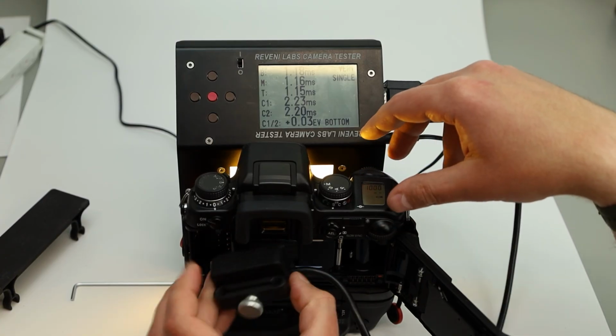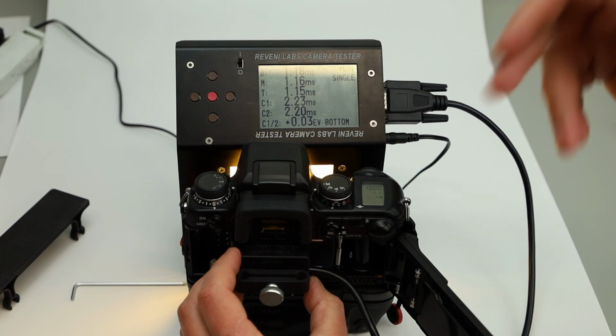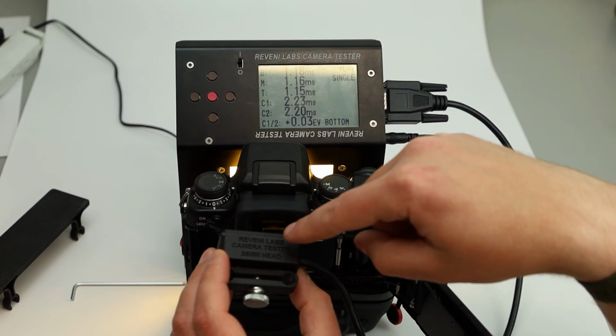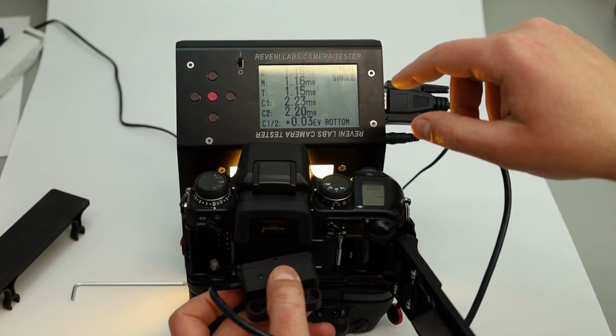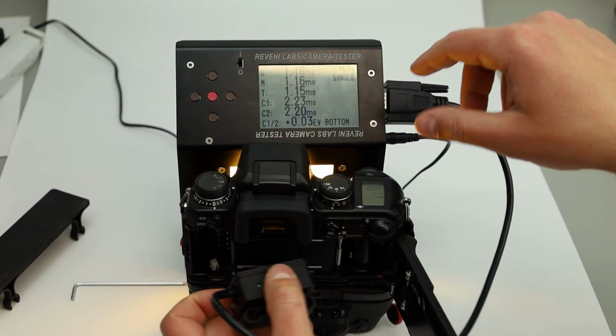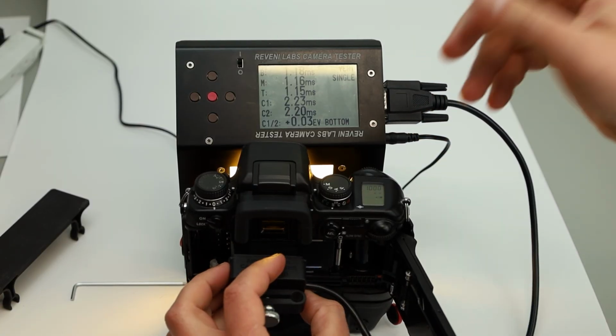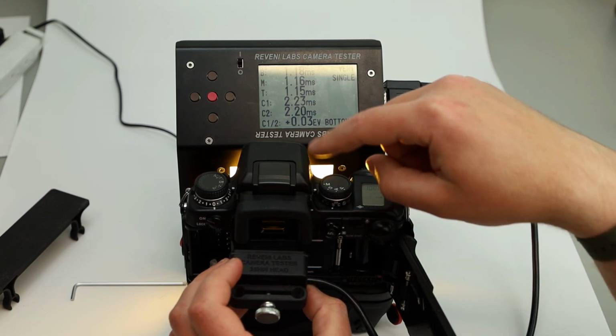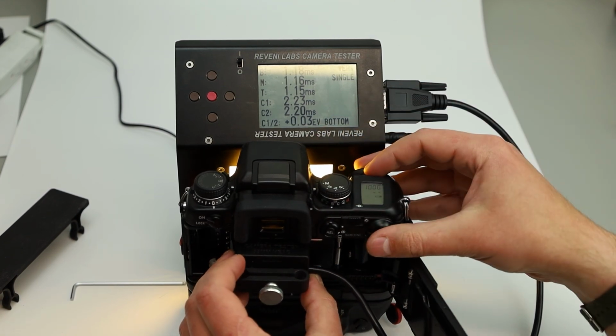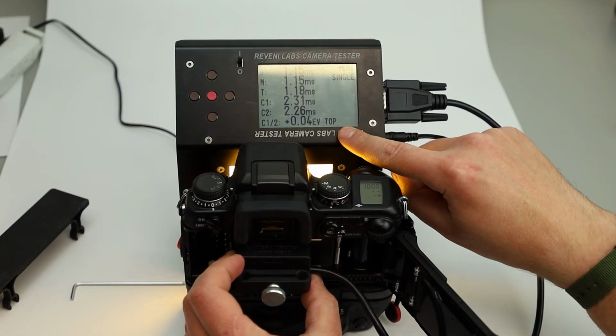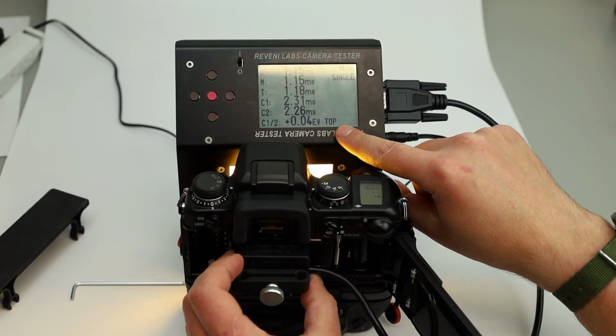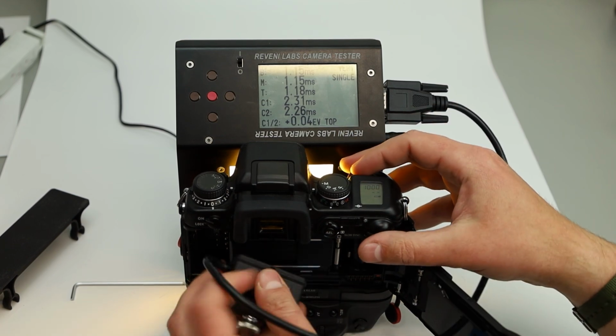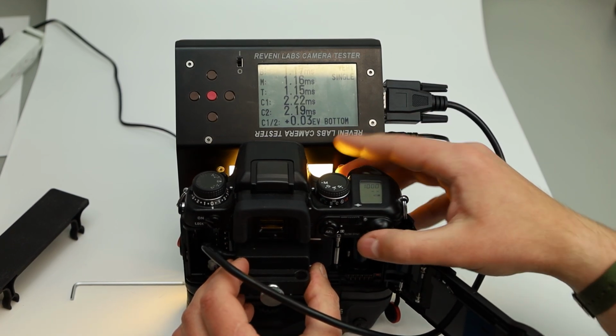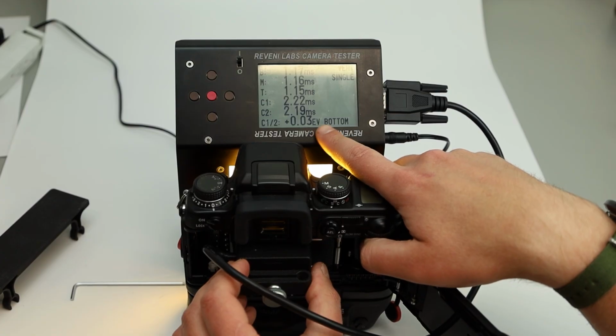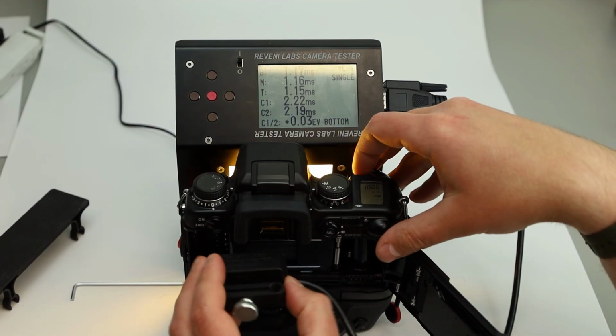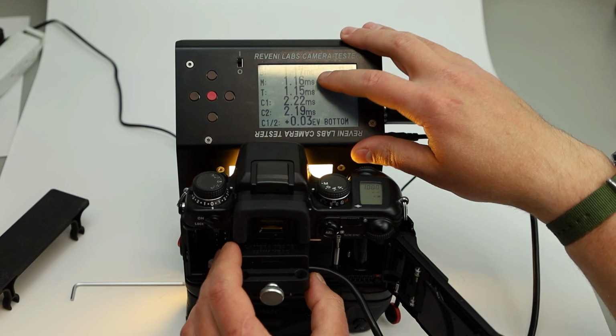If the error had remained the same, even though the sensor head had been flipped, that would mean that it's error in the sensor head because the camera tester does not know which way the sensor is being oriented. We're using that effect to determine error in the head from error in the camera. So every time I flip it, you'll notice it says there's 0.04 EV error topwise. When I flip the sensor over, now it's reading 0.03 error bottomwise.